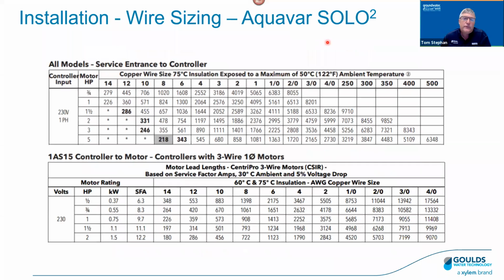Okay. Speaking of drives, one other tip here, let's talk about wire sizing if you have a VFD system. The bottom line is to use the wire charts that come with the product itself, and they should be in the installation manual. The reason is, for example here, we can look at the Solo 2, and we've got all models service entrance to controller. That's what I call the input, right? So for service entrance to controller, there's a chart for that. And then there's another chart, what I would call the output, or controller to motor. So there are two charts that we need to pay attention to when sizing the wire for a drive.